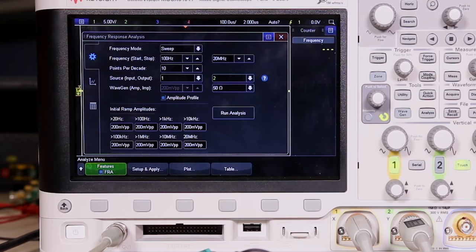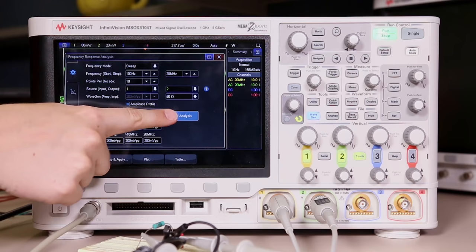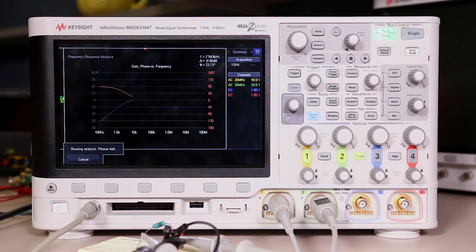So once you have all of these settings configured properly for your specific test you can press run analysis. Now you can see the sine waves actually changing in frequency on the screen and then you can see each of the data points starting to be plotted on the Bode plot as it runs.